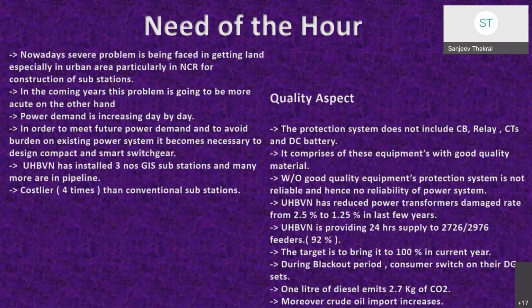UHBVN has constructed 3 GIS substations and many more are in the pipeline. These GIS substations have been constructed in a 25 by 25 square meter area. But now we are struggling to get even this space for construction of new substations. Moreover, the cost of such a substation is around 10 to 12 crore, which is 4 times that of conventional type substations. So the emphasis should be on designing hybrid substations, which are environment friendly, smart and economical too.